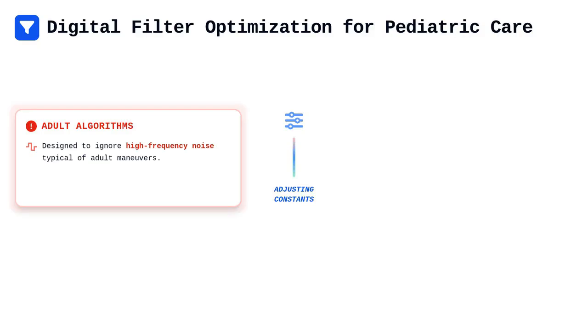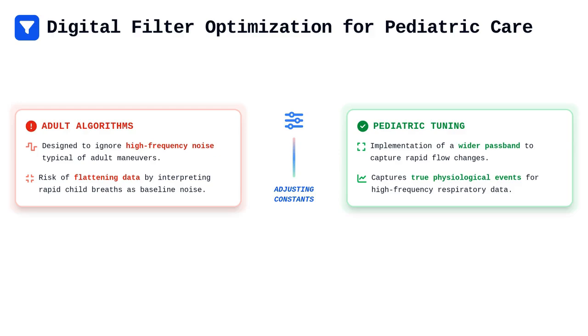Finally, we must adjust the digital filter constants within our software tracking suites to accommodate the physiological pacing of smaller lungs. Adult algorithms usually incorporate smoothing filters designed to ignore high-frequency noise that is expected during adult maneuvers. However, a child's breath can involve rapid flow changes and higher frequencies that these standard filters might inadvertently interpret as baseline noise. By adjusting the digital filter constants to a wider passband, we ensure that the system captures the true, high-frequency respiratory events rather than flattening out the data.